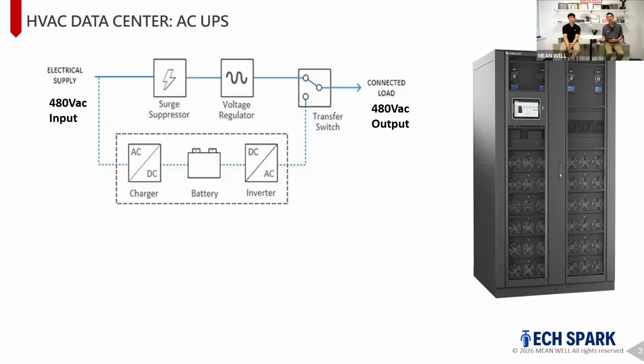So when there's a power outage, the inverter kicks in and does the UPS backup. On the right hand side you see the photo - it's like a double sided 19-inch rack, basically all the inverters and chargers are in there. One of those racks is about 250 kilowatts per module, so for example if the data center is 2 megawatts of power, you need about 8 of them in parallel to do the few minutes of backup for the generator to kick in. These are very, very high power, 250 kilowatt stackable modules.